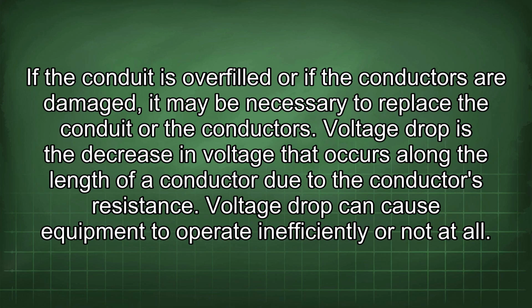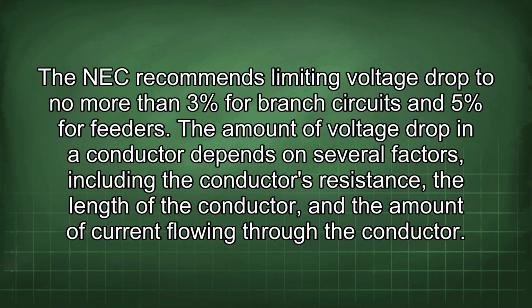If the conduit is overfilled or if the conductors are damaged, it may be necessary to replace the conduit or the conductors. Voltage drop is the decrease in voltage that occurs along the length of a conductor due to the conductor's resistance. Voltage drop can cause equipment to operate inefficiently or not at all. The NEC recommends limiting voltage drop to no more than 3% for branch circuits and 5% for feeders. The amount of voltage drop in a conductor depends on several factors, including the conductor's resistance, the length of the conductor, and the amount of current flowing through the conductor.